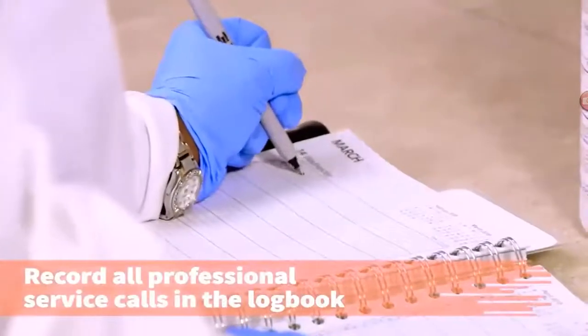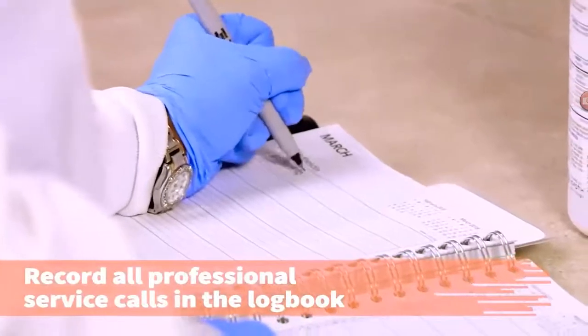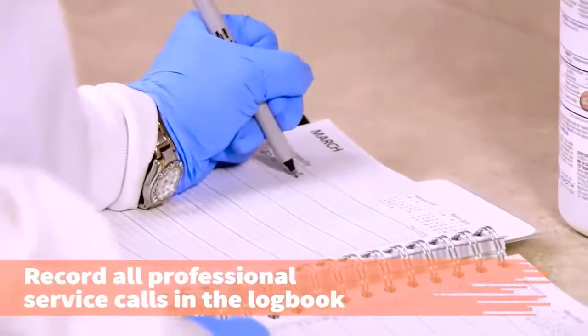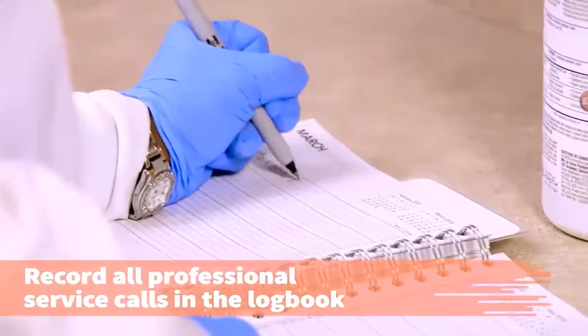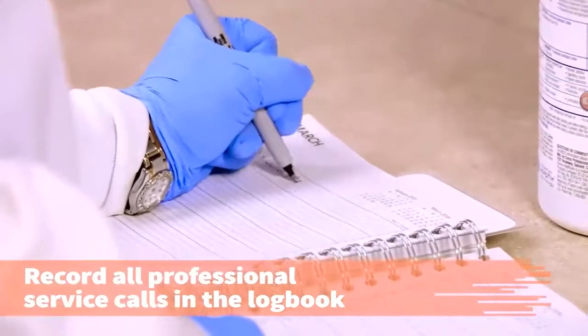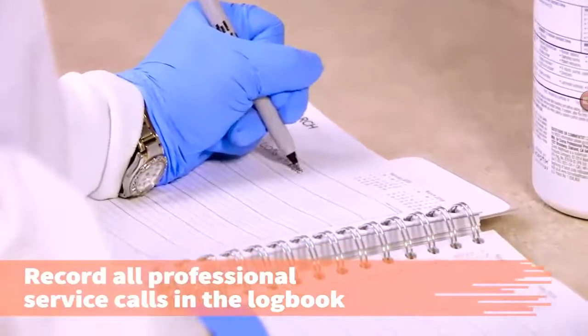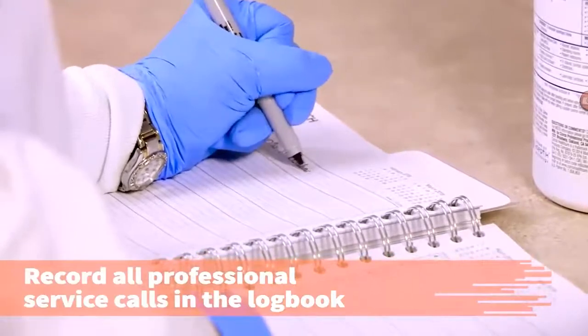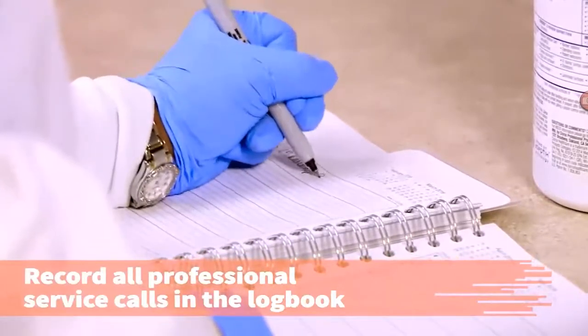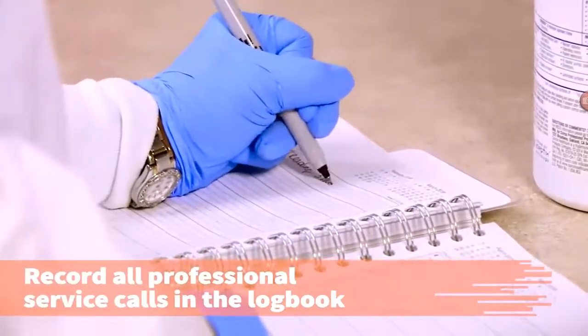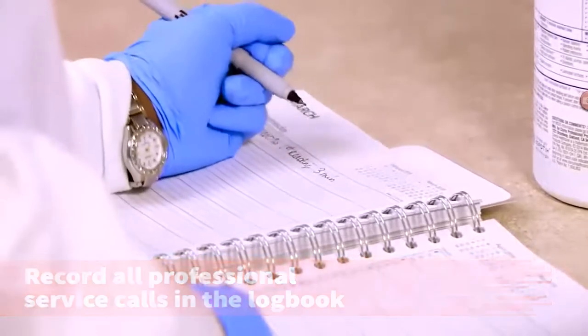Annually, or as needed, the centrifuge functions and maintenance verification should be performed by qualified personnel. This includes checking the centrifuge mechanism, rotors, timer, speed, and electrical leads. Record all professional service calls in the laboratory logbook.